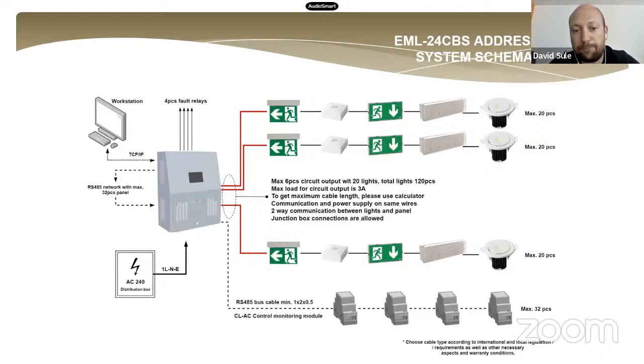I talked about junction boxes being available because it's DC 24 volt. So we can reduce the cable of the circuit, because there is no need to go in and out of every light. We can use a main cable with junction boxes, and we can connect any light in any way. The communication goes the same way as when we connect the lights to each other.